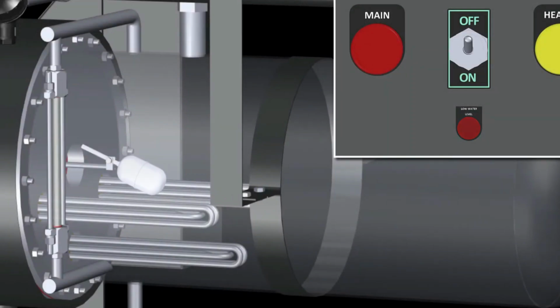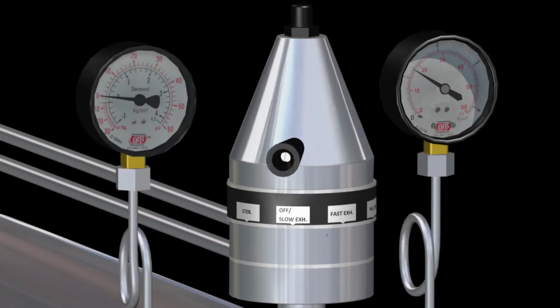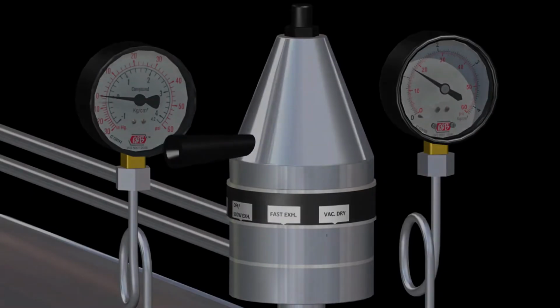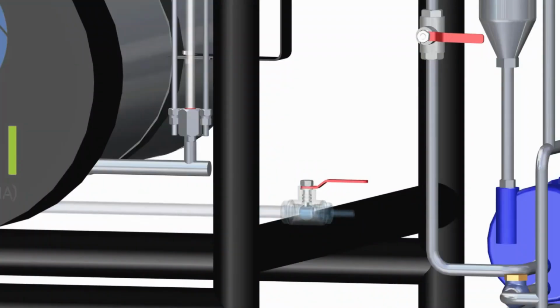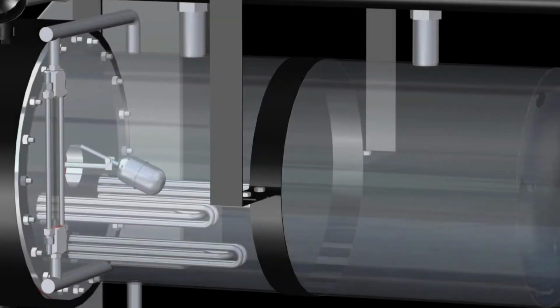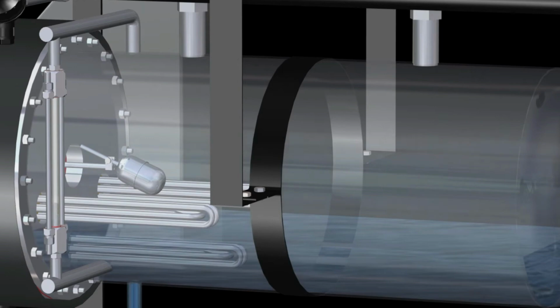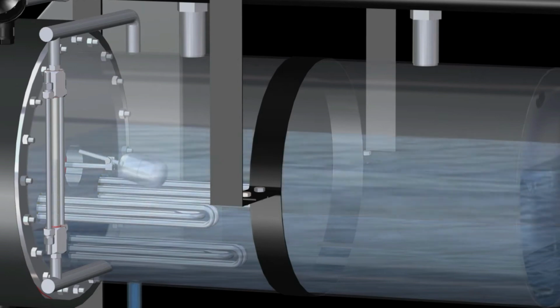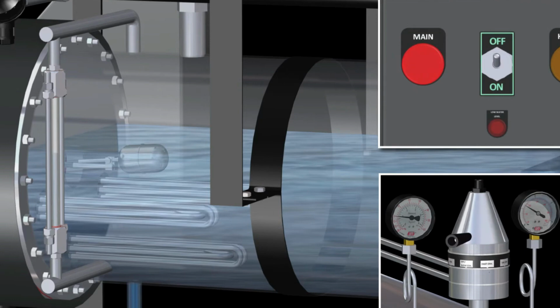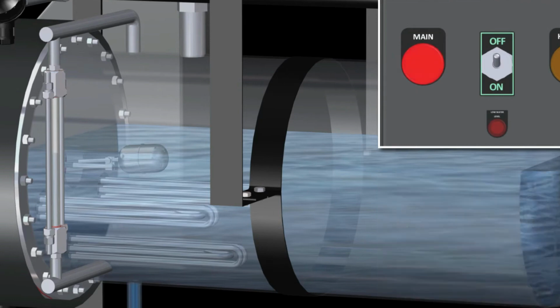Gravity displacement. Steam pushes the air out of the chamber through a vent. Pre-vacuum. A vacuum pump removes air from the chamber before steam is introduced. Steam flush pressure pulse, SFPP, alternates between steam injections and vacuum pulses. Sterilization. Steam injection. Steam is introduced into the chamber.